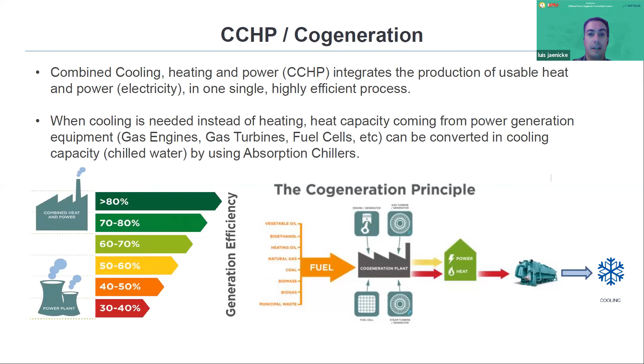For example, it could be a gas engine, or a gas turbine, or a fuel cell, but all the heat that is generated by this power generation equipment is not released to the ambient, it's not lost. It is recovered by heat recovery equipment. And all this heat is sent to absorption chillers that convert the heat into the cooling that is needed by the data center. I'm still fascinated how an absorption chiller can transform heating into cooling, but they do so, and therefore it is a perfect match for the data center, which is power hungry but also cooling hungry. So it's a perfect match to do cogeneration at site, produce your own electricity at a more efficient rate, cleaner, but also use all this available heat to produce the cooling demand of the data center.